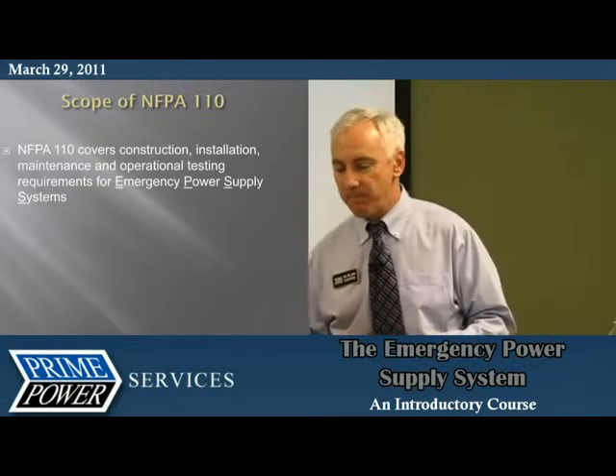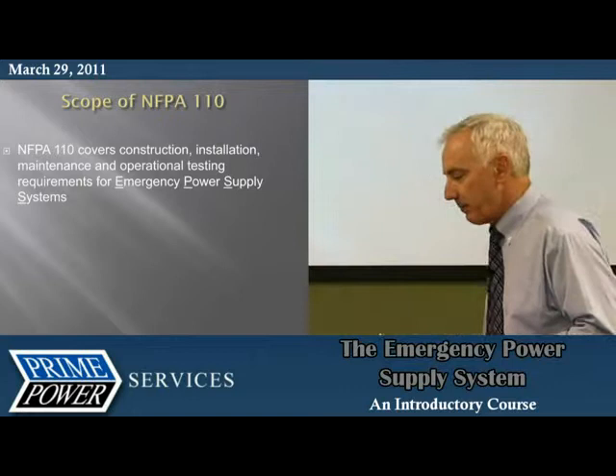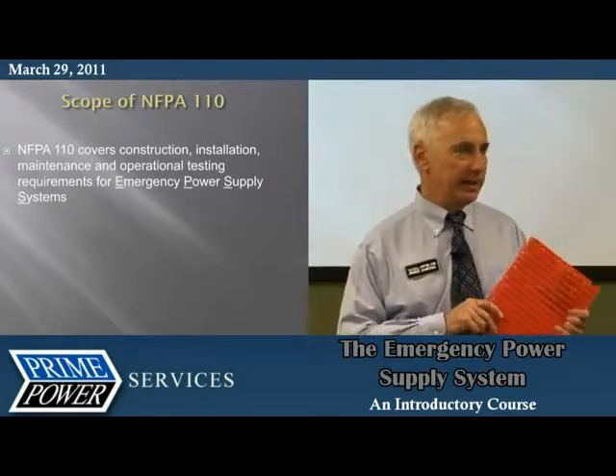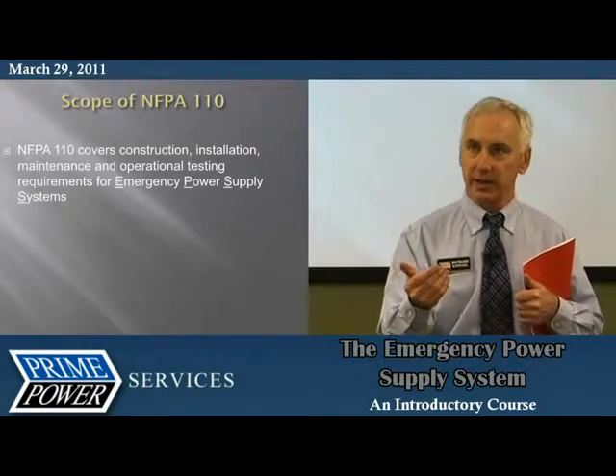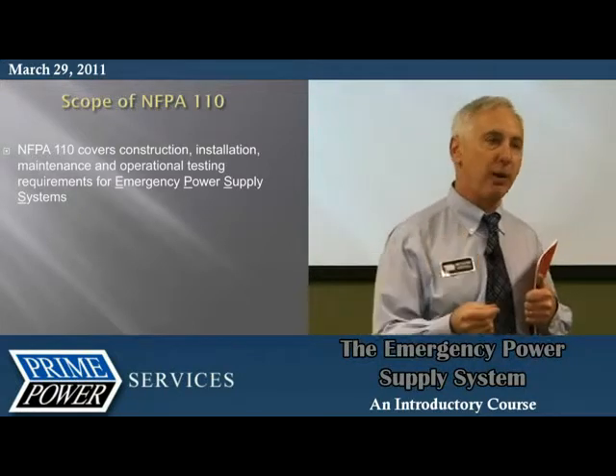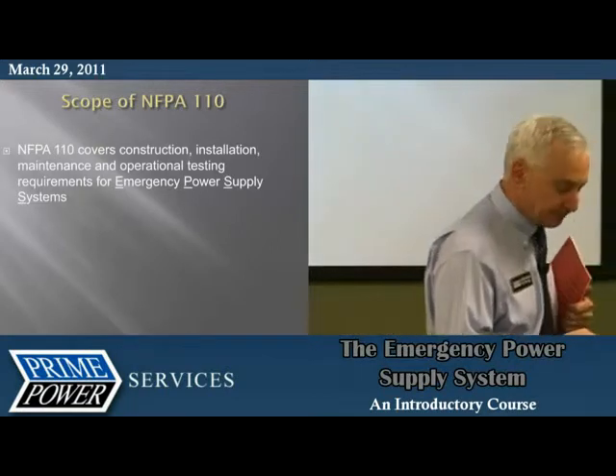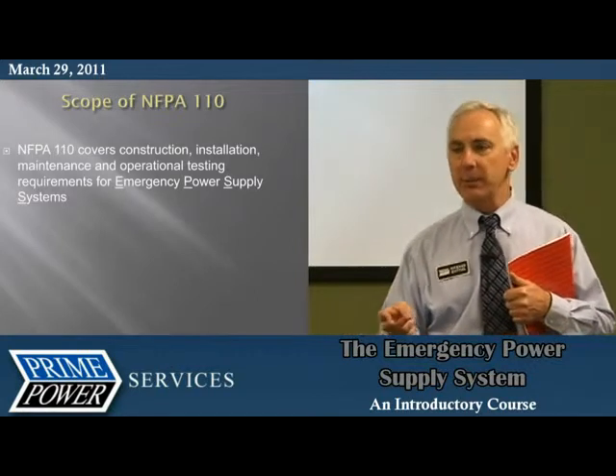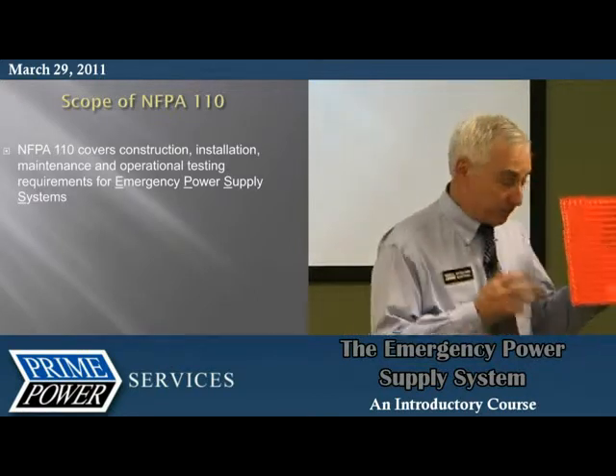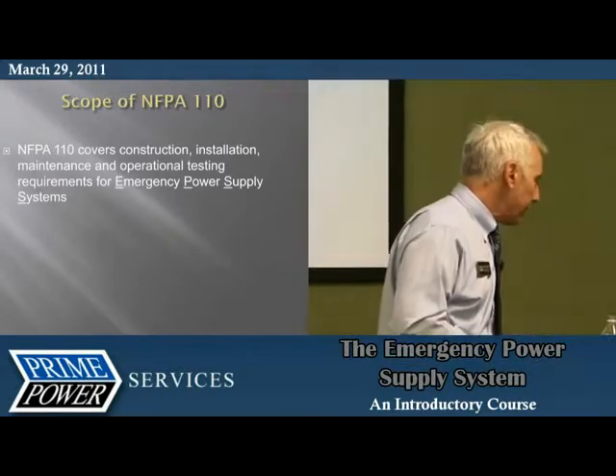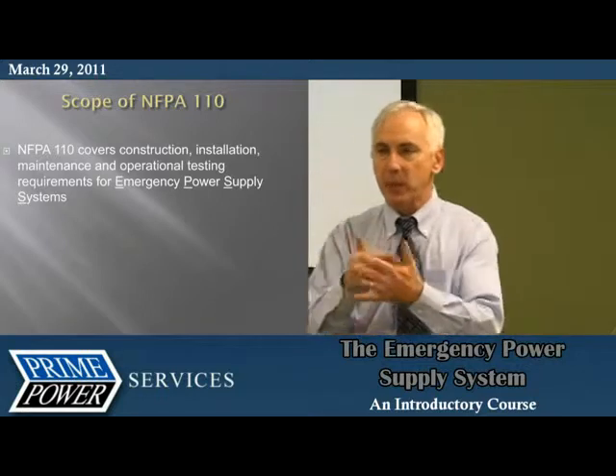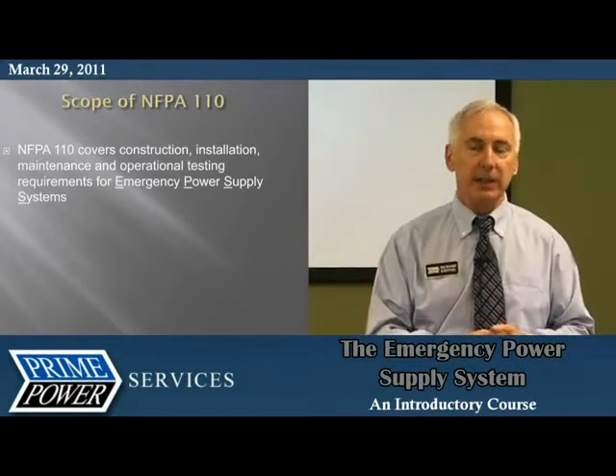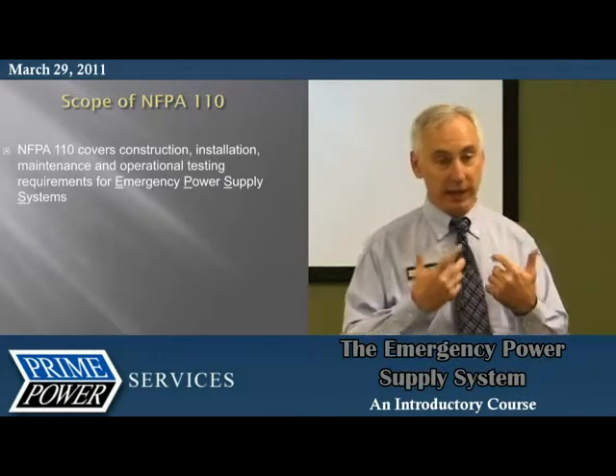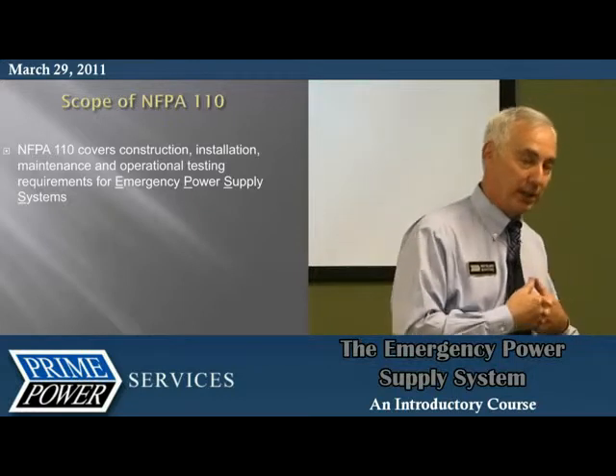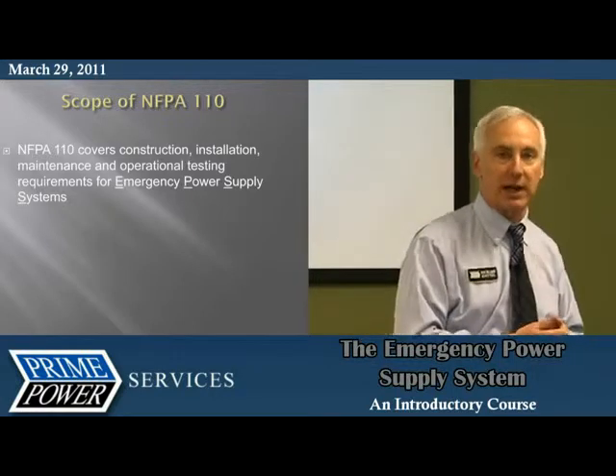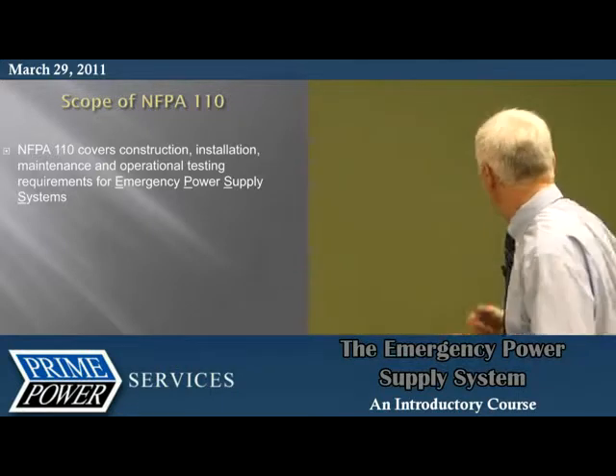The other reason we push this is that having an emergency generator implies to whoever is under that you are providing emergency power for data, lighting, or whatever. That implication puts the liability on you that you are maintaining this. So if there were ever a negative issue and somebody comes back and says, to what standards are you maintaining this, you need to be able to answer that question. Hopefully not, but if it comes up, you need to respond. So we use this as our guide. It's kind of a liability issue.